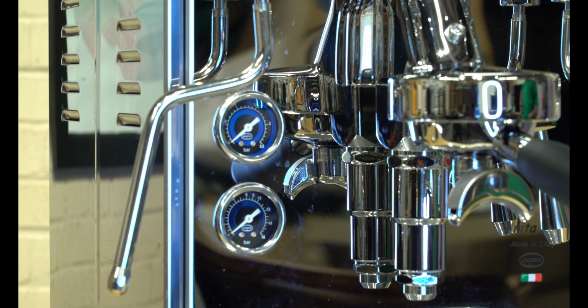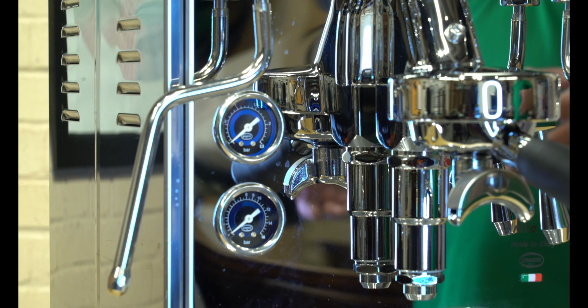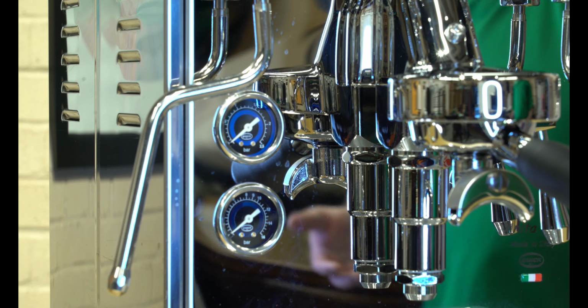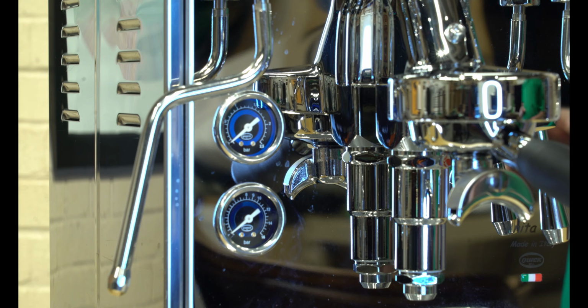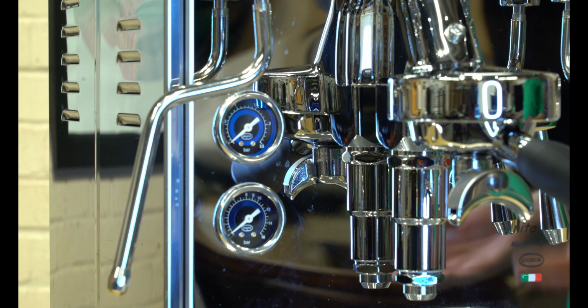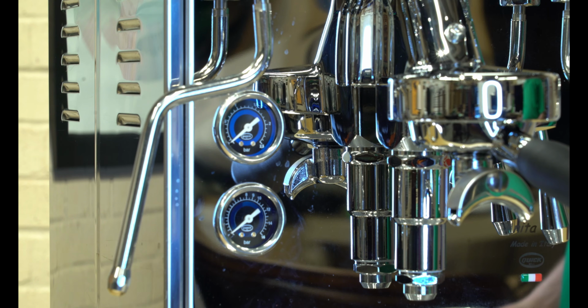So I wanted to reorient the machine real quick. This machine does have dual manometers. It's a pressure stat machine, which is an older technology, but that helps save money by not having PID features. If you're not familiar with those terms, a PID is kind of like a thermostat for your house — you set the temperature and it maintains that based on the number you put in.